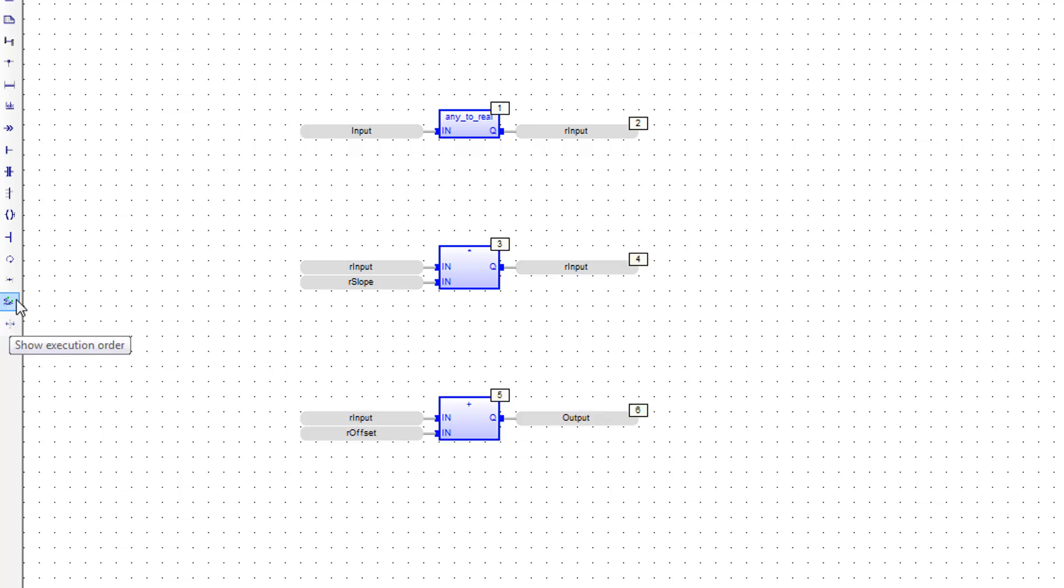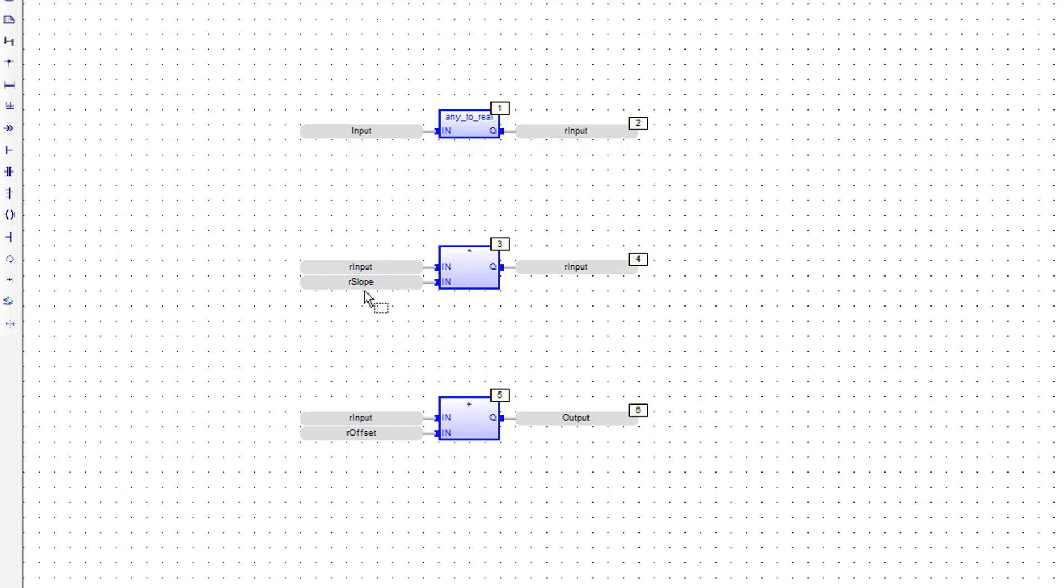This shows you how the steps will execute. So it will take the input, convert it to a real, and then it will take the real input and multiply it by the slope and put it back into that input variable. And then it will take the input and add the offset to it and put it into the output variable.